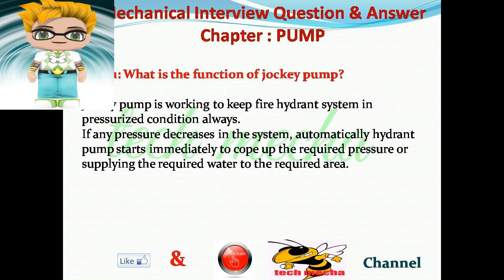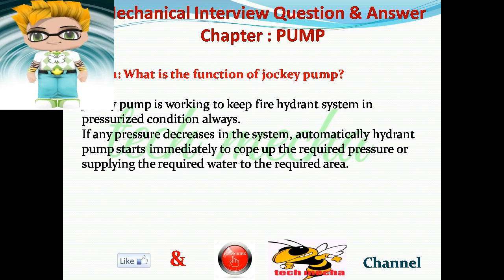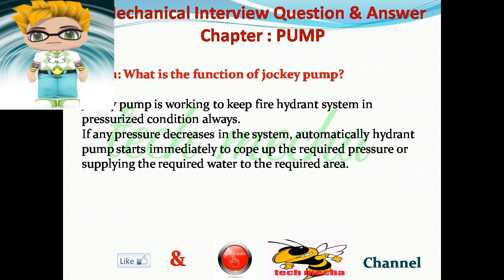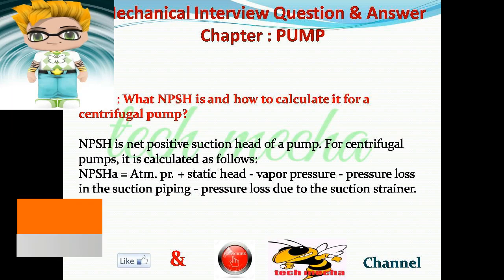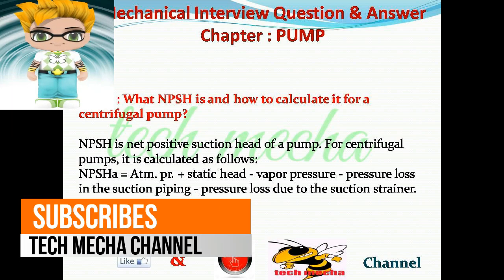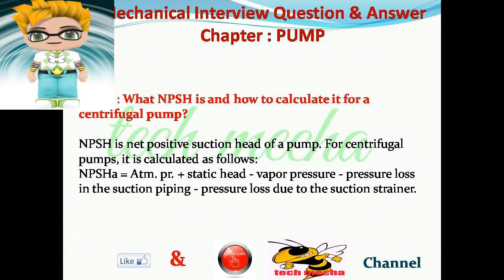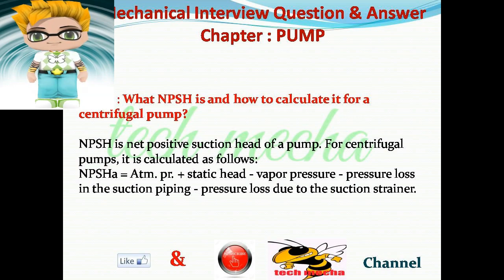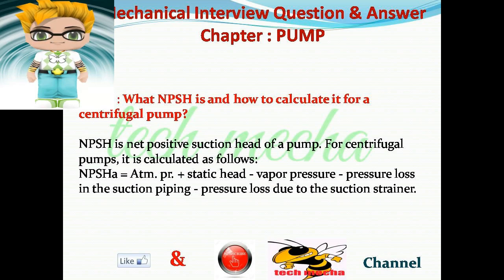Question number 11: What is the function of a jockey pump? Answer: A jockey pump works to keep the fire hydrant system in a pressurized condition always. If any pressure decreases in the system, the hydrant pump starts automatically to supply the required pressure or water to the required area. Question number 12: What is NPSH and how is it calculated for a centrifugal pump? Answer: NPSH equals atmospheric pressure plus static head minus vapor pressure minus pressure loss in the suction piping minus pressure loss due to the suction strainer.